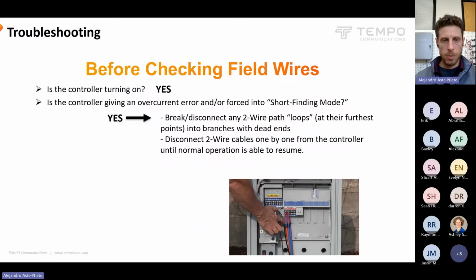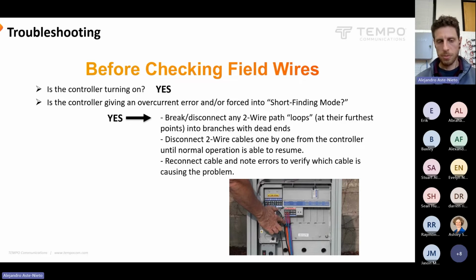So once we've done that, we're going to want to disconnect the two-wire paths, the two-wire cables, one by one from the controller, and see if that changes anything. See if our controller says, oh, the problem has gone away. Once we do that, we can verify that the cable path is the one introducing that problem. We can try to reconnect the cable and see if it all of a sudden starts working and that was just a fluke and there's no problems now. Or if you reconnect the cable and the error returns or the shutdown happens again, you verify that there is currently a problem on that wire path.